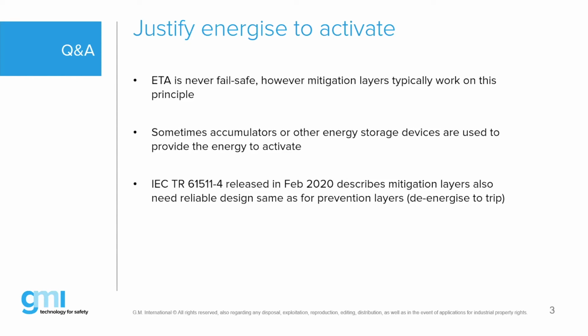But simply speaking, I'll give you a small example of a gas sensor application, from a discussion I had on a project in Europe. The gas mapping of your sensors is also part of the success of your story. That means the mapping of the sensors is most likely more important than the SIL specification of the sensor itself. In other words, if you put a SIL2 sensor in your plant, but the wind is blowing the gas in the wrong direction and the SIL2 compatible sensor cannot sniff it or recognize it, well, the SIL integrity of your device may be very good, but it cannot work as the wind is blowing in the wrong direction. That means fire mapping and gas sensing mapping are also part of the success of your story. Yes, Mauro.